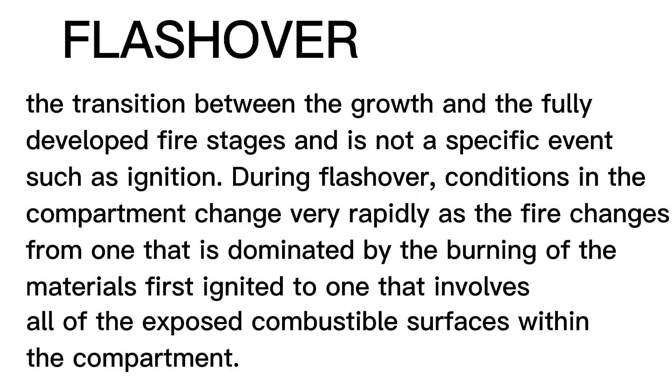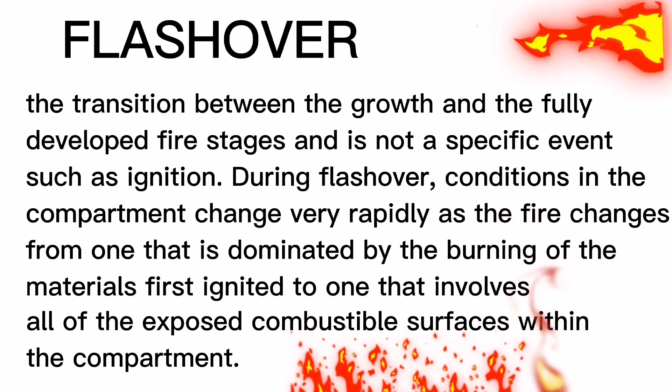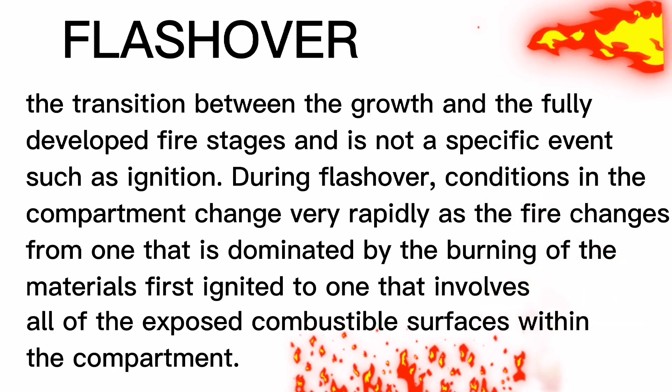Flashover — the transition between the growth and the fully developed fire stages — is not a specific event such as ignition. During flashover, conditions in the compartment change very rapidly as the fire changes from one dominated by the burning of the materials first ignited to one that involves all of the exposed combustible surfaces within the compartment.